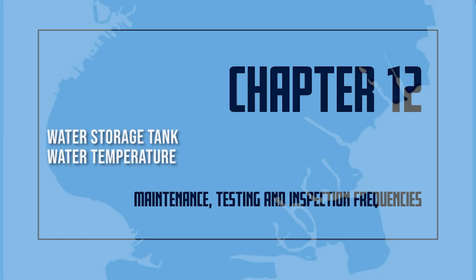The temperature of water in the tanks without low temperature alarms connected to a constantly attended location shall be inspected and recorded daily during the heating season. The temperature of water in the tanks with low temperature alarms connected to a constantly attended location shall be inspected and recorded weekly during the heating season. Air pressure. Air pressure without a supervised air pressure source shall be inspected monthly. Air pressure with a supervised air pressure source shall be inspected quarterly.